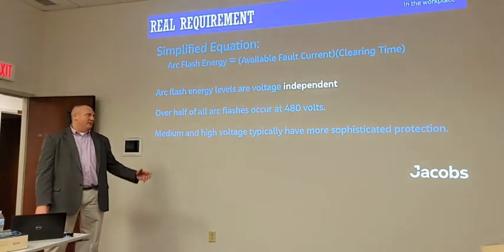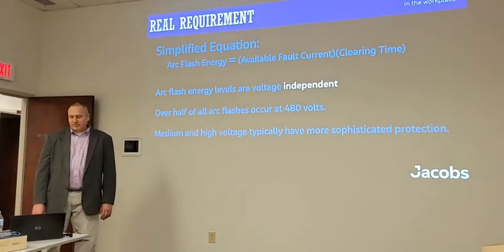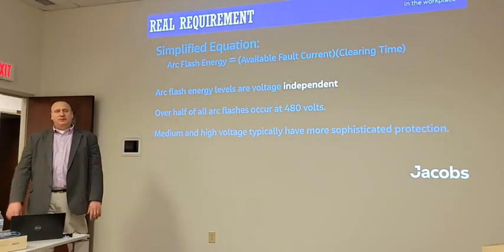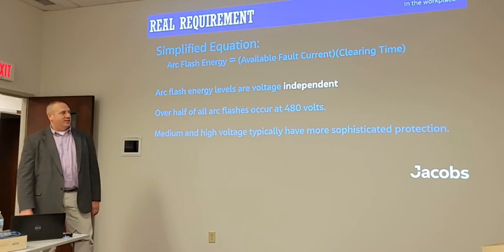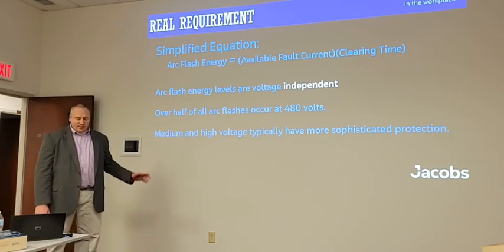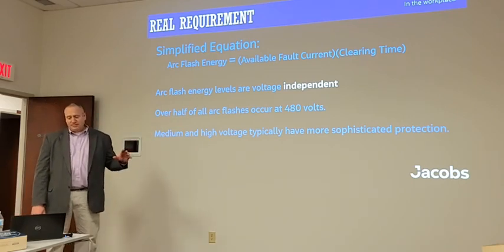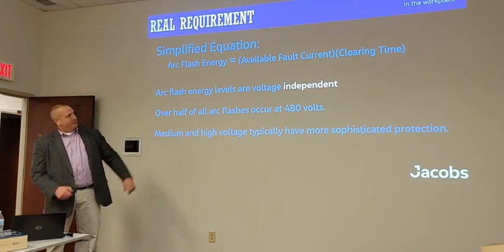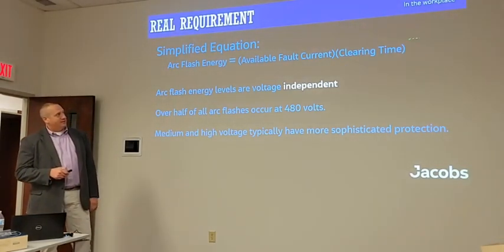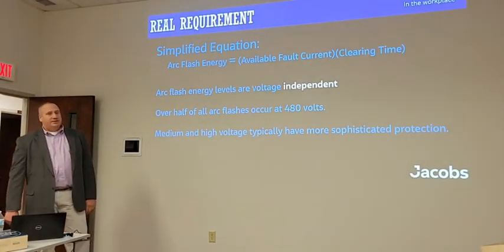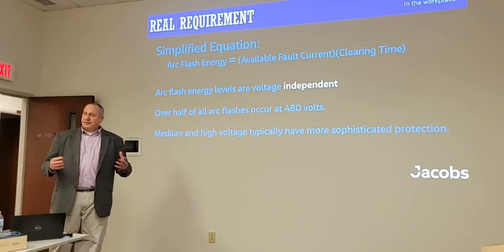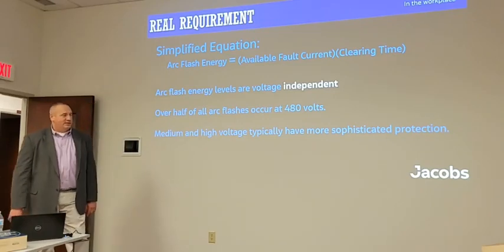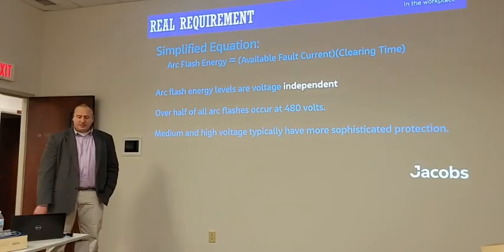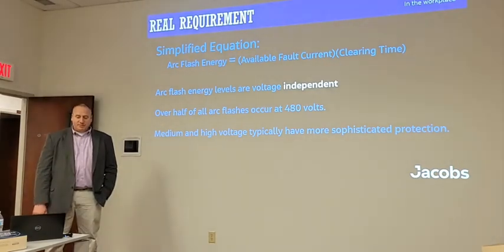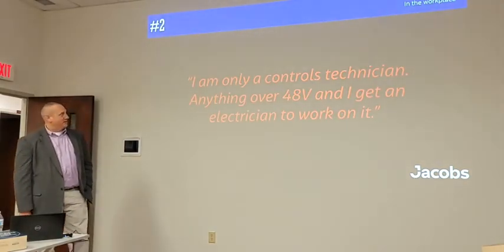Whereas when you get to the 480 volt systems, you're happy if you've got a thermal magnetic or overcurrent protective device. That's one of the reasons why, because clearing time, again at the top there, is one of the factors in your arc flash energy. So the more sophisticated your protection is, the quicker the clearing time is, and your arc flash energy reduces. So it's not voltage dependent.